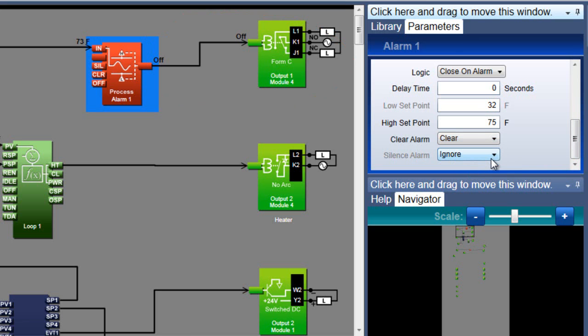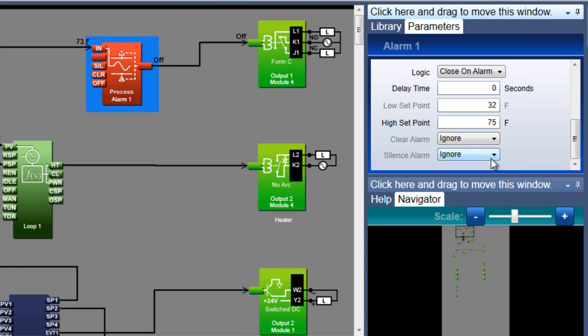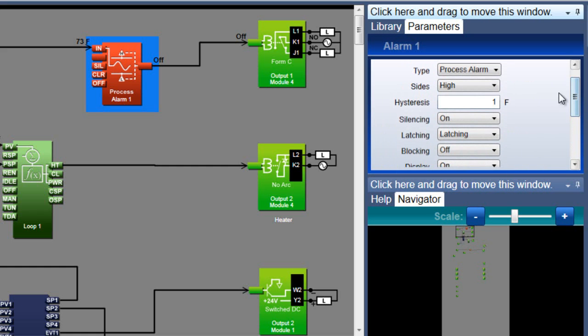Because the temperature drops quickly in this example, it's hard to see, but I can't clear the alarm until the temperature is one degree below the high setpoint. To require that the actual temperature drop 3 degrees below the alarm setpoint, I'll change hysteresis to 3.